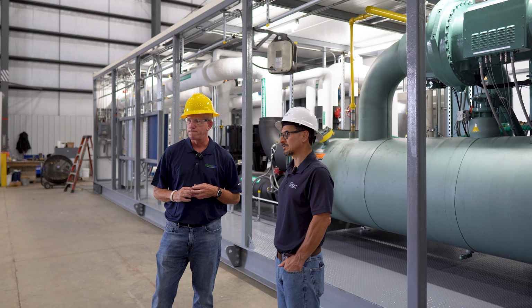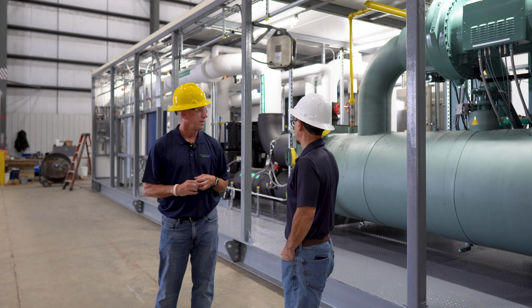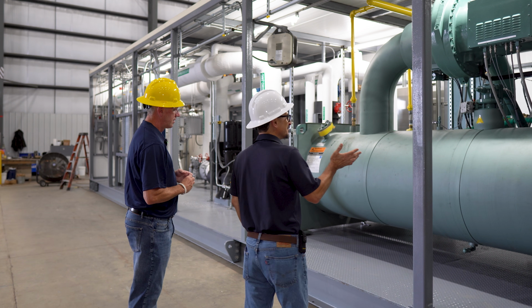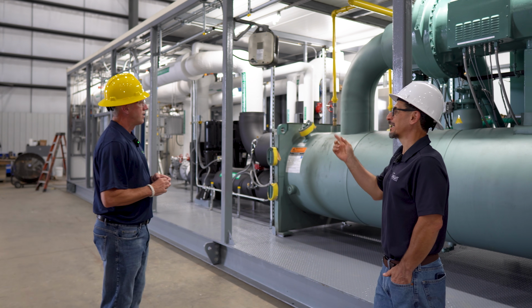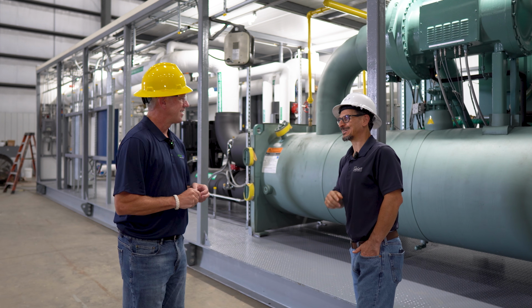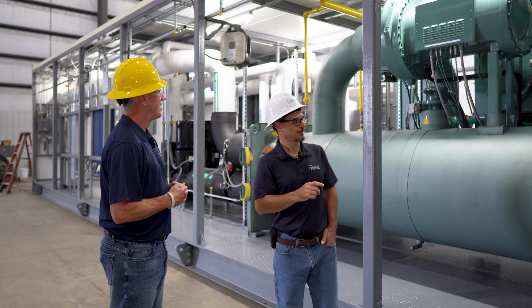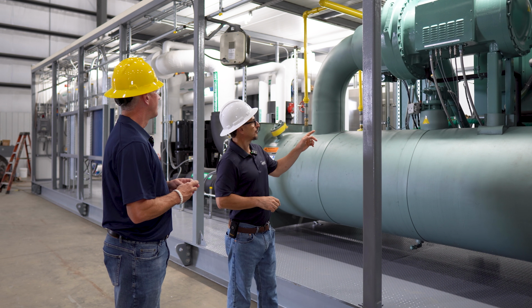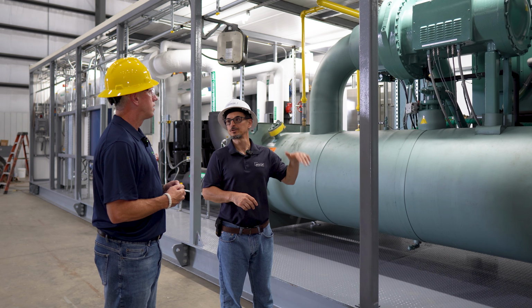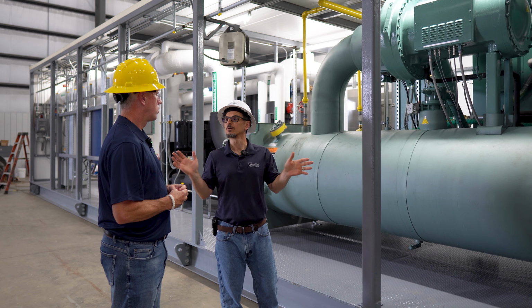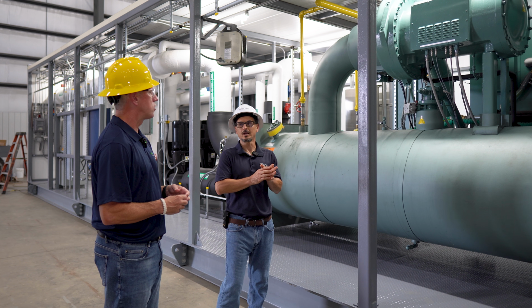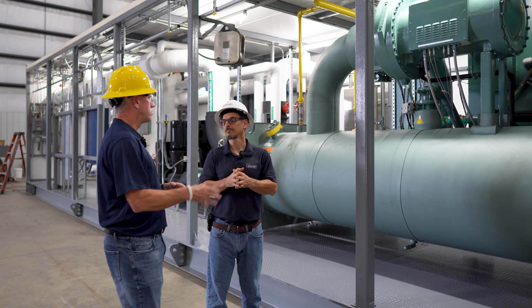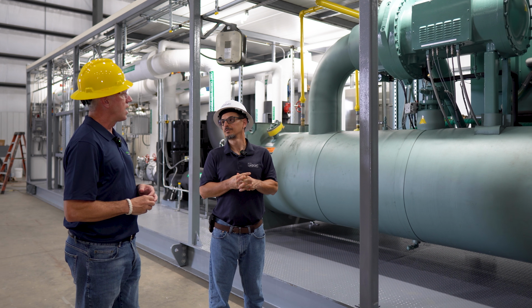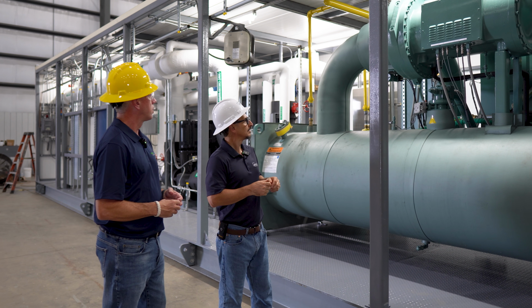Before we get a tour of this nice looking Marley stainless steel tower, maybe we could talk about the motor. What I couldn't remember last time, open motor design, because it's been a while since I've looked at centrifugals, but this is a hermetically sealed motor, or the refrigerant is cooling the motor, or it's liquid cooled. This one is liquid cooled. This is the YMC squared chiller. So it's liquid cooled, and this is their magnetic bearing chiller.